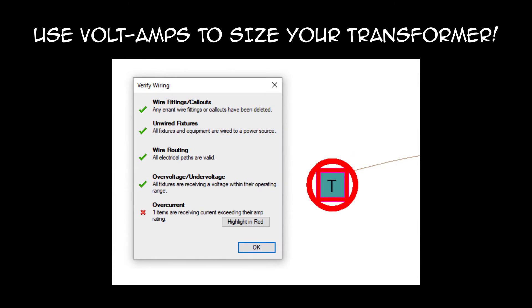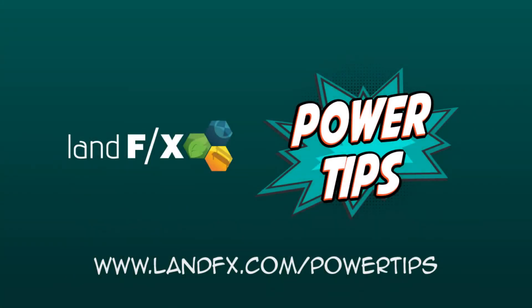Moral of the story: use the sum of your light fixture's volt amps to size your transformer. Otherwise, you'll have a bigger mess on your hands than spilled beer. For more videos like this one, visit landfx.com/powertips, or check out the LandFX phone app.